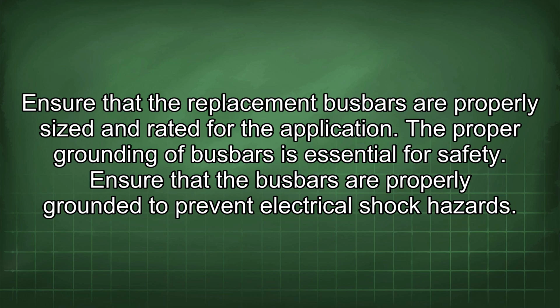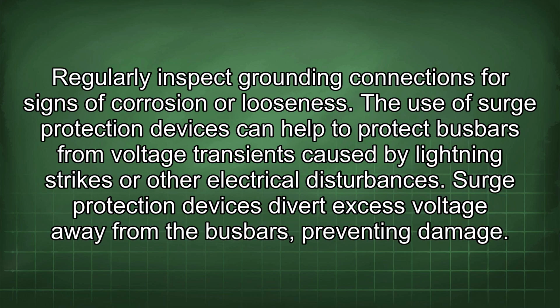The proper grounding of busbars is essential for safety. Ensure that the busbars are properly grounded to prevent electrical shock hazards. Regularly inspect grounding connections for signs of corrosion or looseness. The use of surge protection devices can help to protect busbars from voltage transients caused by lightning strikes or other electrical disturbances. Surge protection devices divert excess voltage away from the busbars, preventing damage.